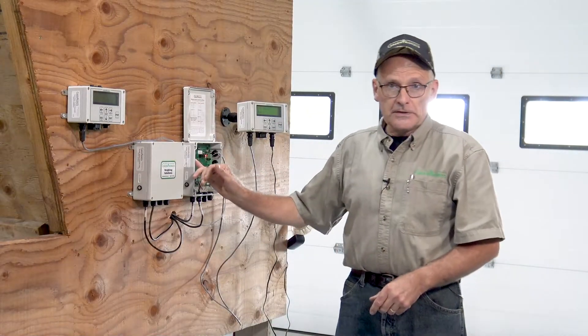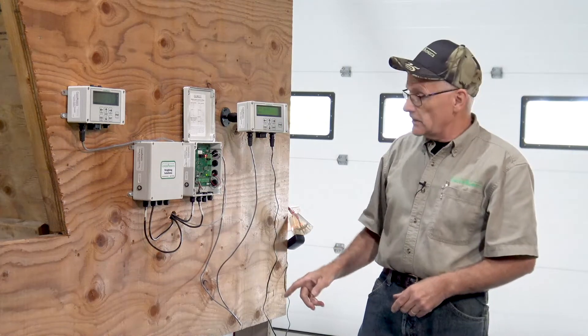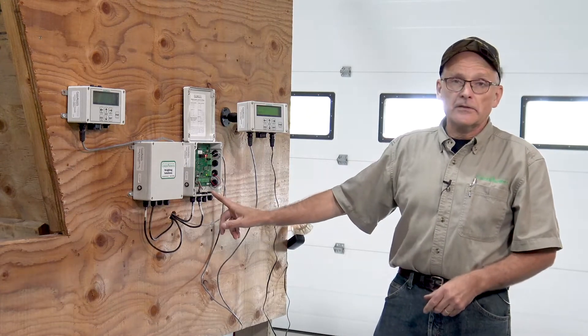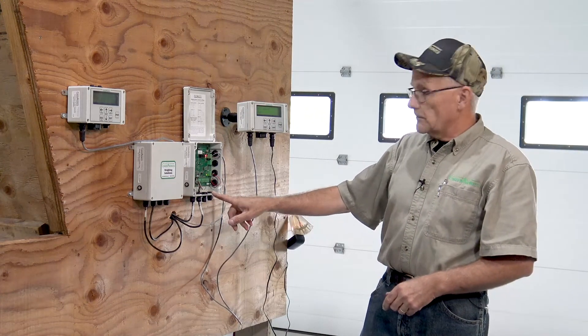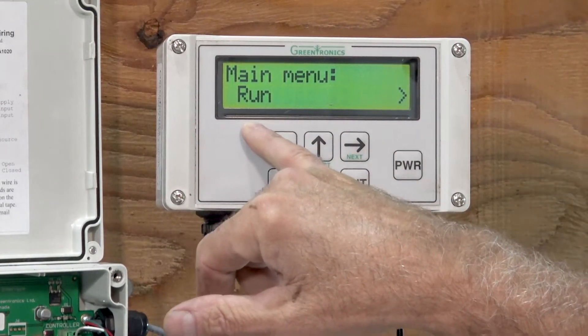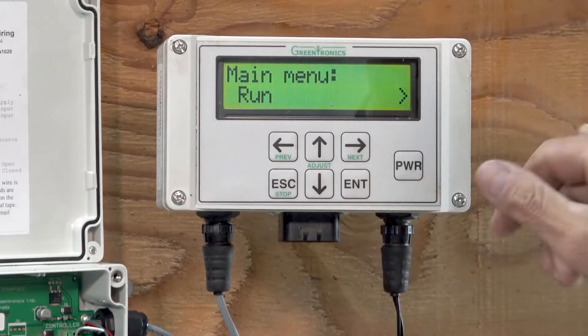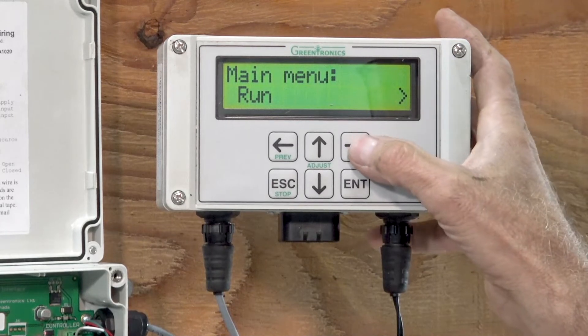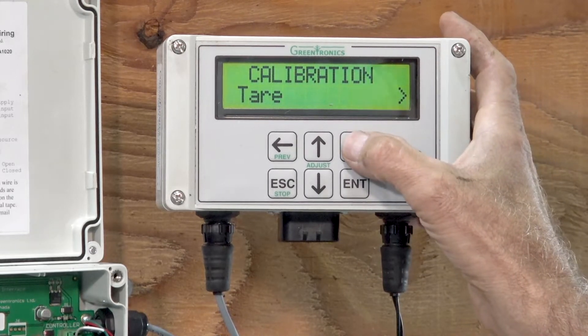After we've confirmed that the junction box is connected properly and we've got the right indicator lights on, my next step is to go into the calibration menu and look at the load cells and make sure that they're configured correctly. The console comes up at main menu run when you first power it on. There's an arrow key indicating we can go right to more menus, and I'm going to go to the calibration menu. The first one that comes up is tare, but we want load cells, so I go to the fourth one and enter here.